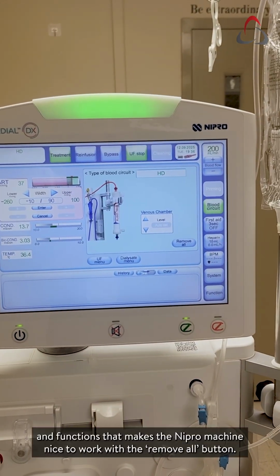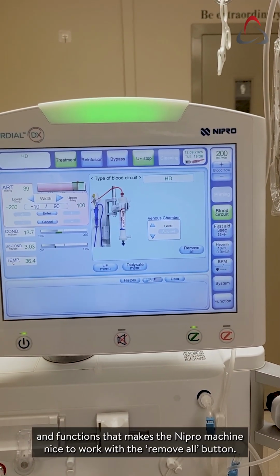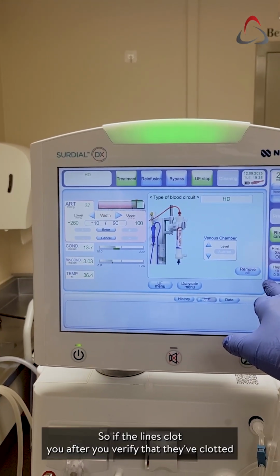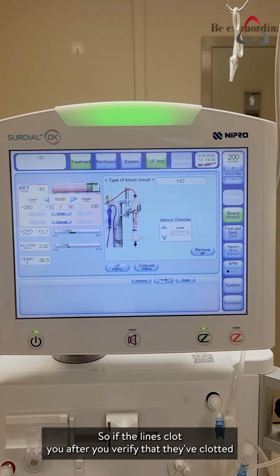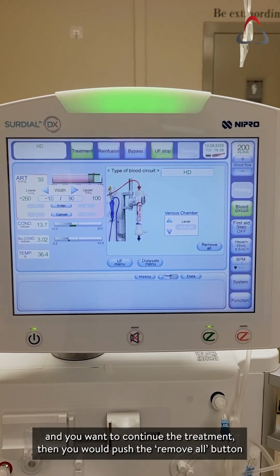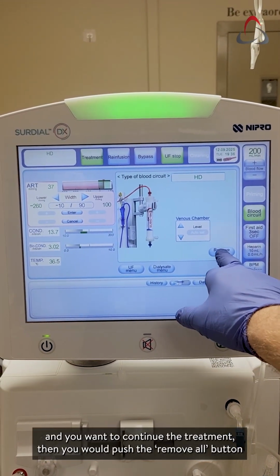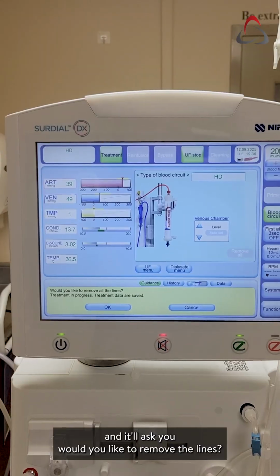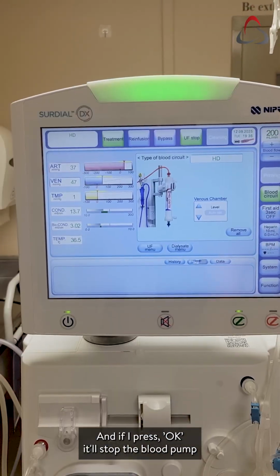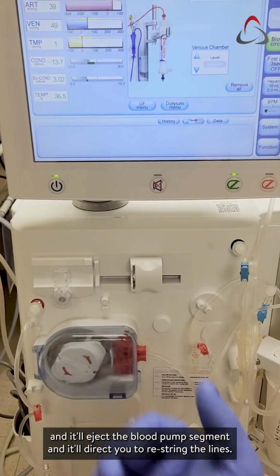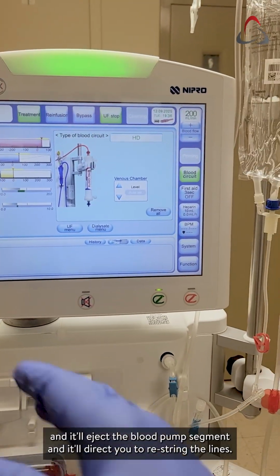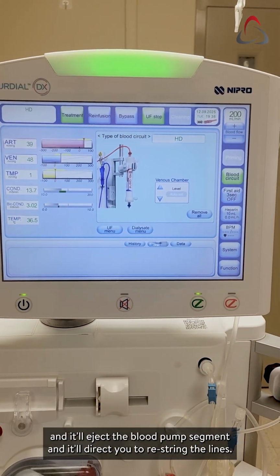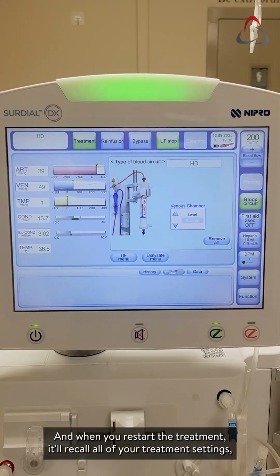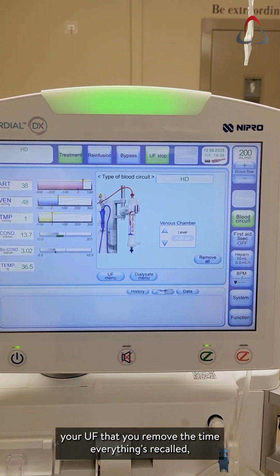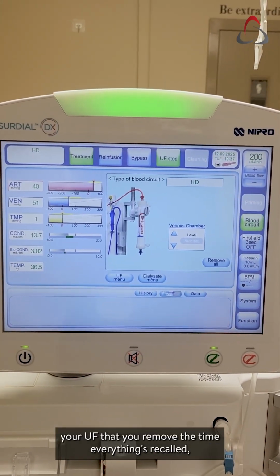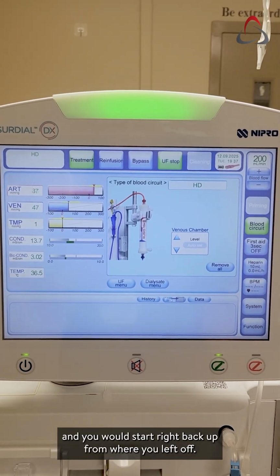Some other settings and functions make the Nipro machine nice to work with. The remove all button: if the lines clot, after you verify that they've clotted and you want to continue the treatment, you push the remove all button and it asks, would you like to remove the lines? If I press OK, it stops the blood pump, ejects the blood pump segment, and directs you to restring the lines. When you restart the treatment, it recalls all of your treatment settings, your UF that you removed, the time. Everything's recalled and you start right back up from where you left off.